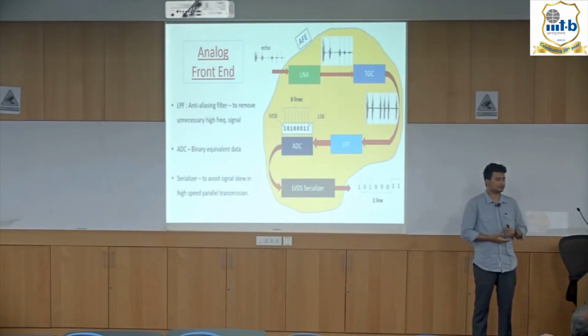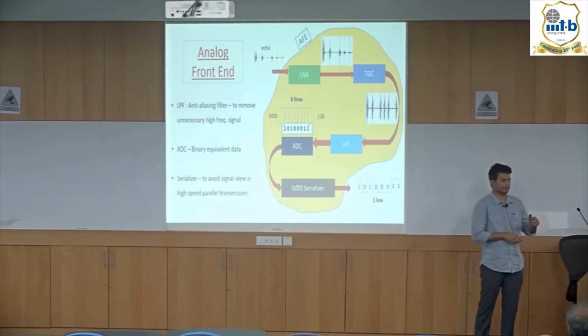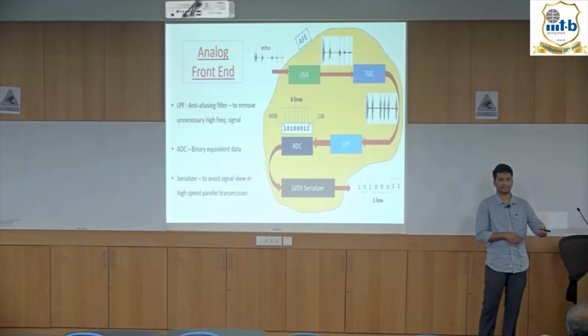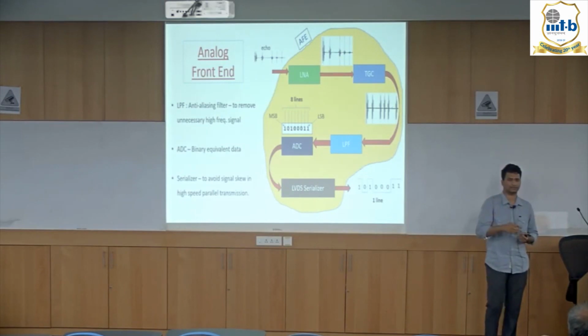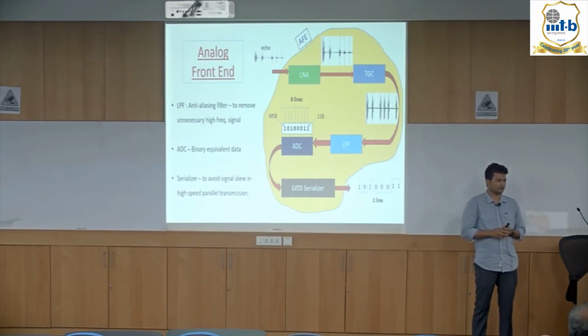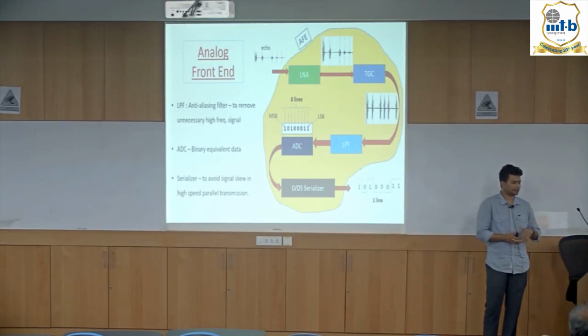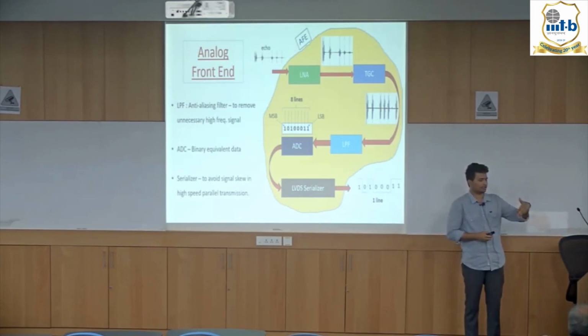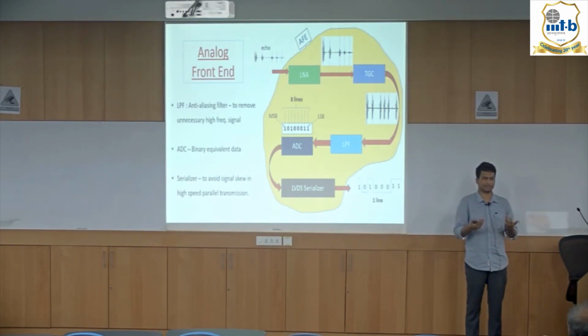So here, since the ADC is typically of high speed, because the echo signal itself is in megahertz, to sample it we go for 40 or 50 or sometimes 100 megahertz of sampling rate. Once the ADC samples and converts the data, it might give out data in 14, 16, even higher bits, depending on the resolution of the ADC.